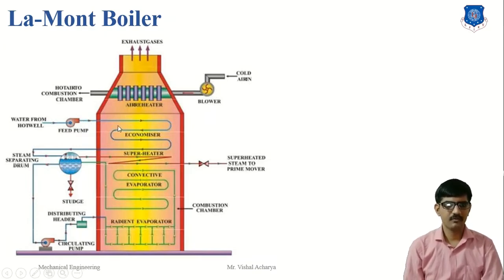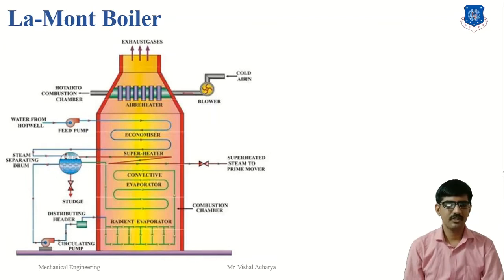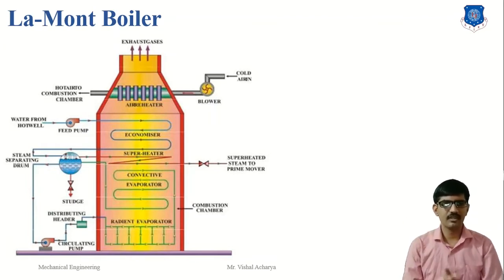In the Lamont boiler working: first, the feed pump circulates water into the economizer, where the temperature of the water increases slightly. The water is then transferred to the steam separating drum. From the steam separating drum, water is circulated to the radiant evaporator using a centrifugal pump, providing forced circulation so the pressure inside the tube is higher compared to natural circulation.